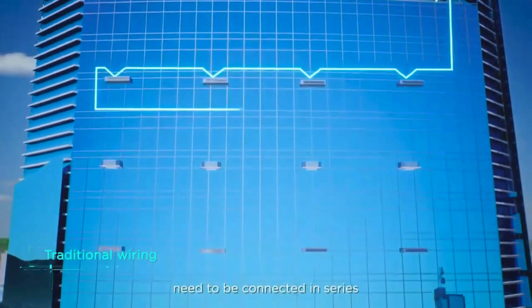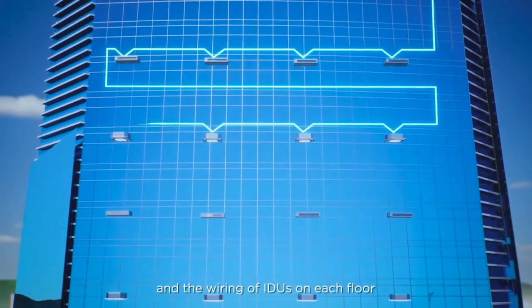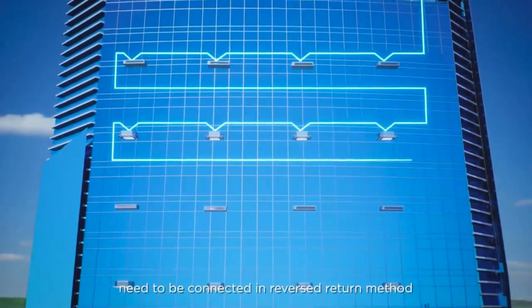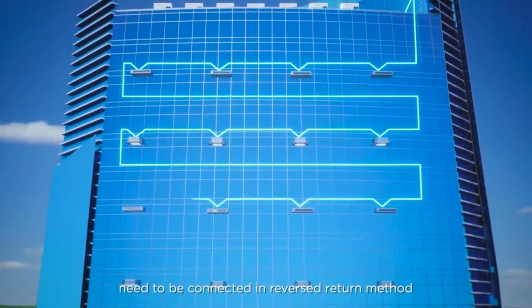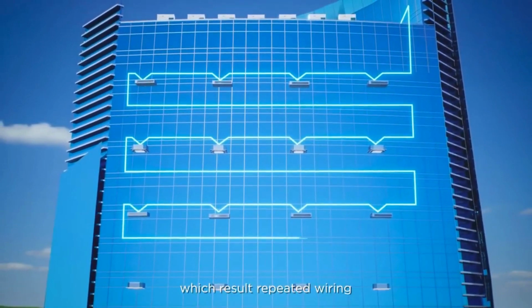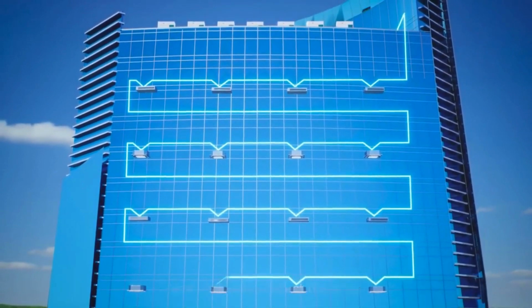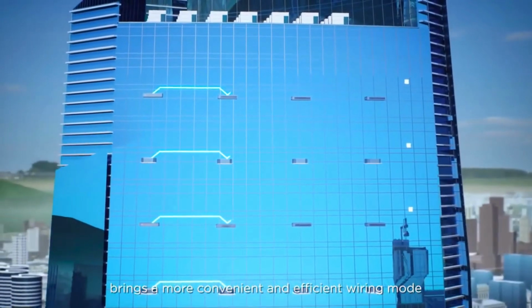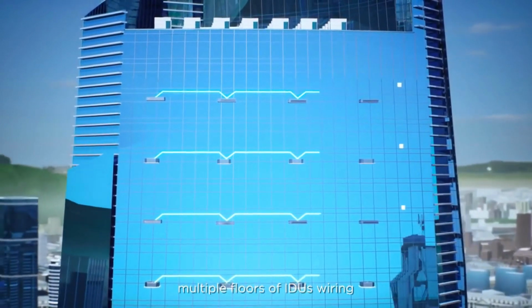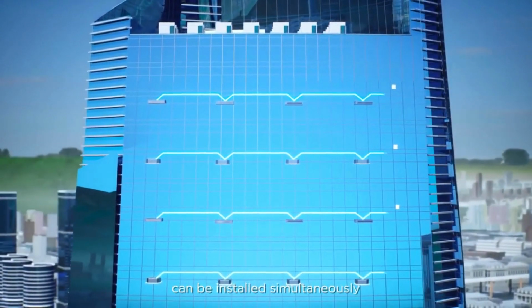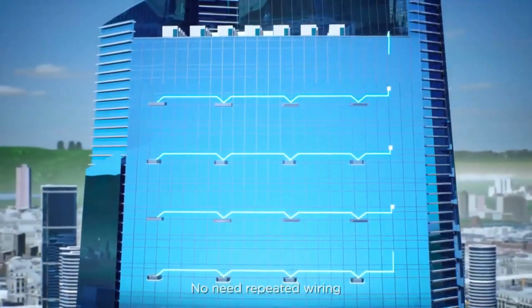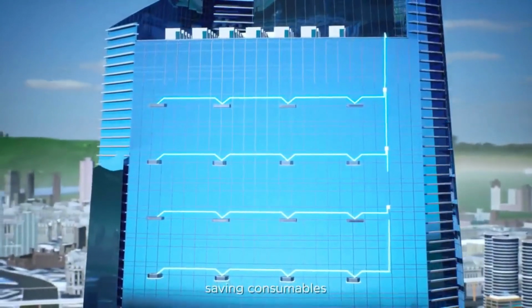The traditional VRF indoor units need to be connected in series, and the wiring of indoor units on each floor need to be connected in reverse return method, which results in repeated wiring, and it's hard to detect errors. With the new wiring mode, multiple floors of indoor units wiring can be installed simultaneously. No need for repeated wiring, saving consumables.